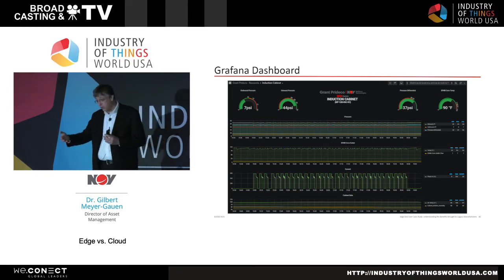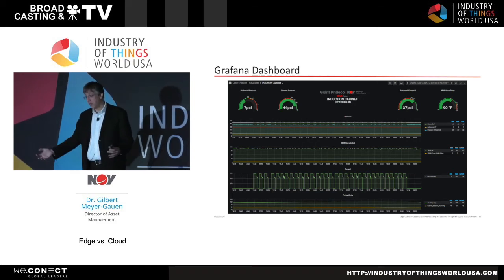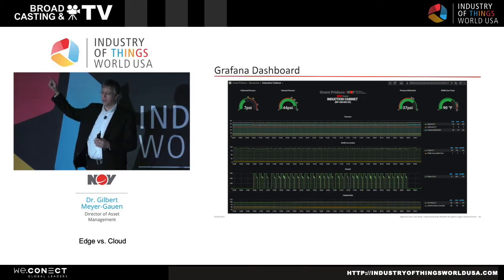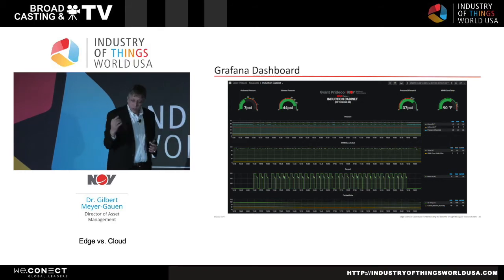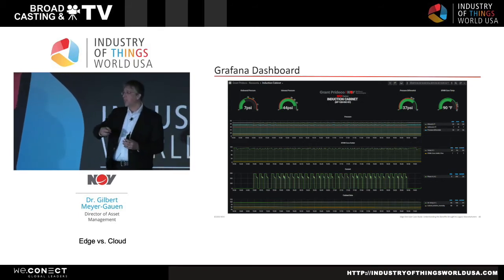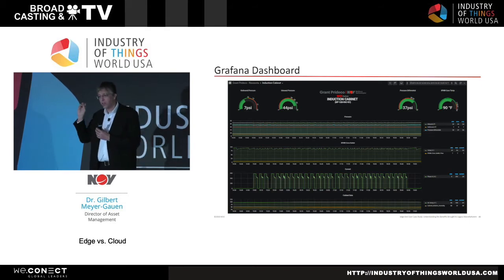And the oil was getting into the water. So now we not only had a completely messed up oil bin that had to be cleaned, we also had oil in the water reservoir because these cooling cycles are closed. So a solution in this case could have been that the edge device would have shut down the machine immediately if it would have recognized water in the oil bin.